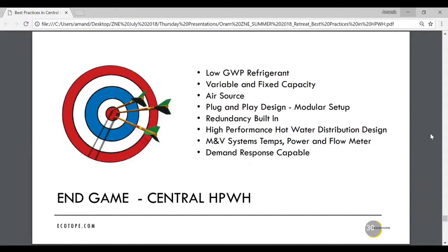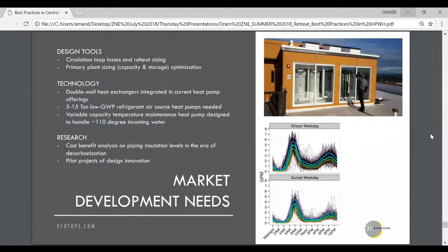So here's the end game with central heat pumps, in my opinion. Low GWP refrigerant is very key. Variable and fixed capacity heat pumps, air source, plug and play design, making sure you've got redundancy built in. All of the systems we've been doing have backup electric boilers on them. We've had to rely on them when things go south, but so far we haven't had problems on this one, I told you. Obviously the high performance hot water distribution design, M&V systems are really crucial in this early stage. And then making sure they're demand response capable. I think that's kind of where things should be heading.